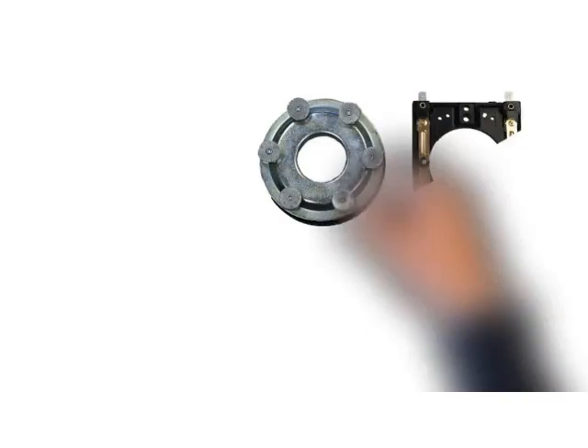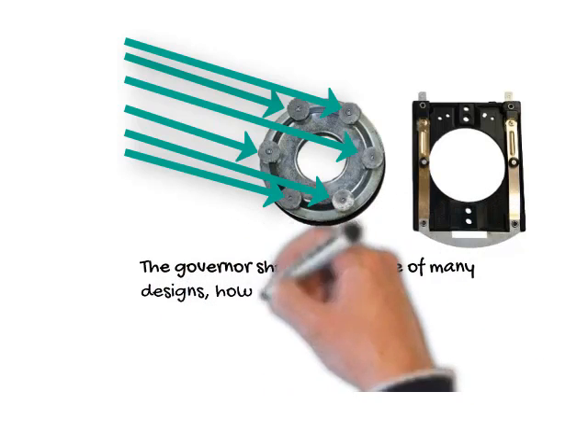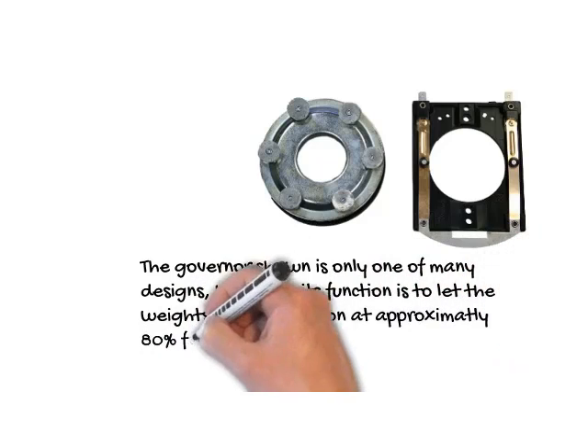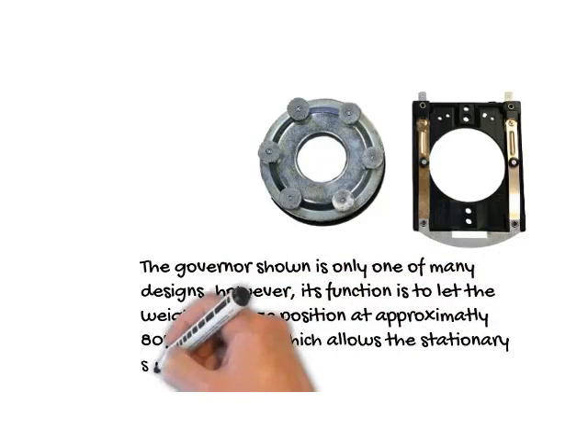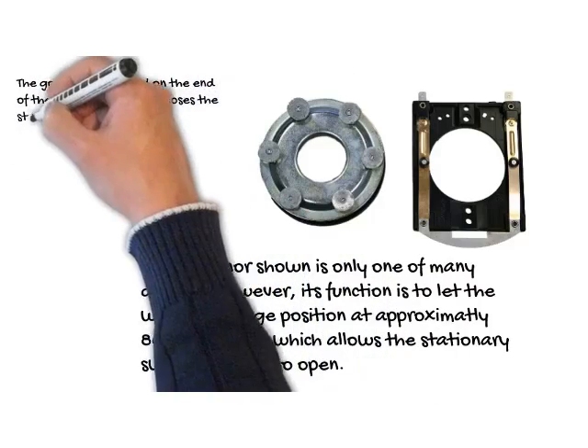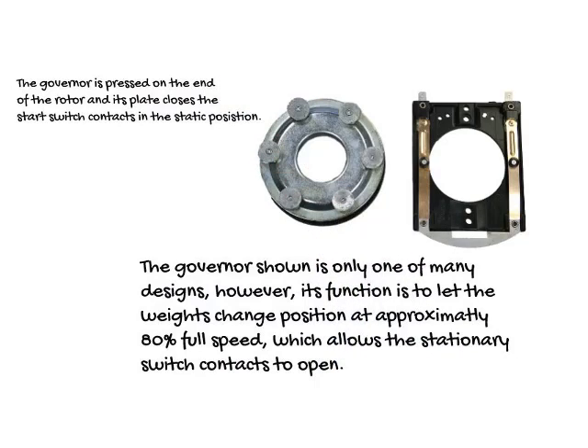The governor shown is only one of many designs. However, its function is to let the weights change position at approximately 80% full speed, which allows the stationary switch contacts to open. The governor is pressed on the end of the rotor and its plate closes the start switch contacts in the static position.